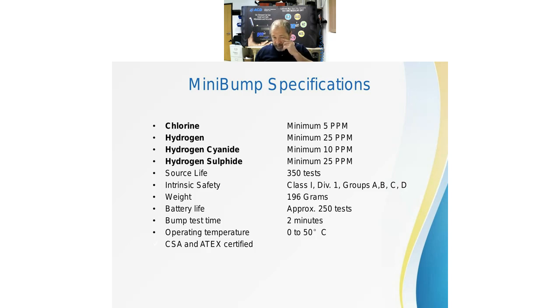Now on the bump side, so these are just the bump test cells that don't put out an exact amount of gas, they just bump some gas. These are about what comes out of there. So the chlorine comes out about 5, hydrogen's about 25, HCN at 10, and H2S at about 25. What happens is you just press the button on the front of that, it runs on 2 AA batteries. It passes current through the cell for a minute, and then a pump inside kicks on and pushes some gas out. And we're just going to functionally test, make sure that sensor's working or that gas detection system altogether is working. So you can make sure all the lights come on and the sirens sound and everything is working as you want it to be working on a functional test, but not set the exact ppm level of your sensor.